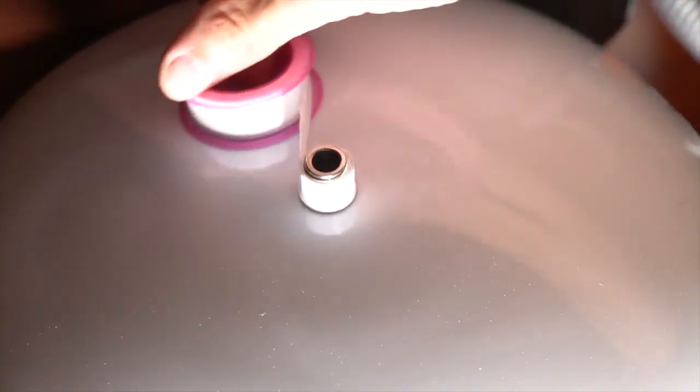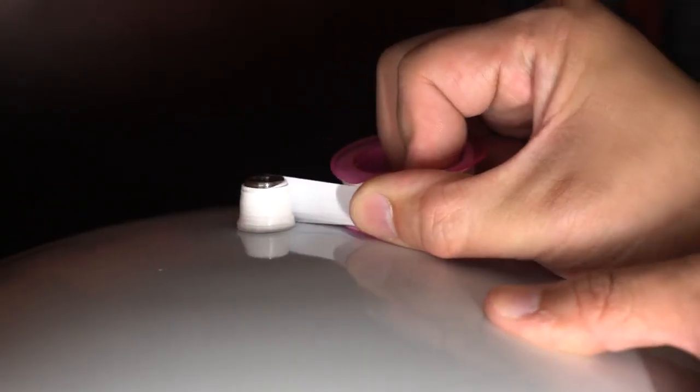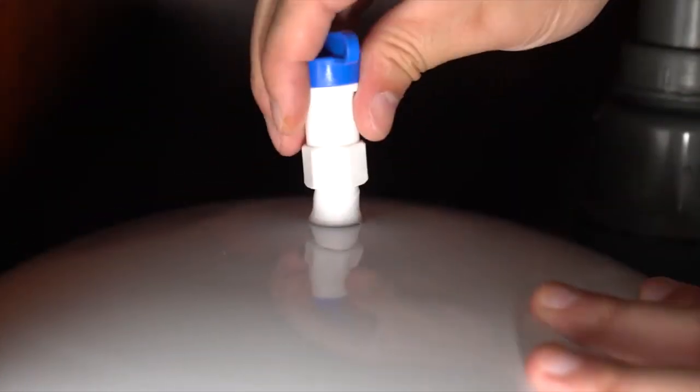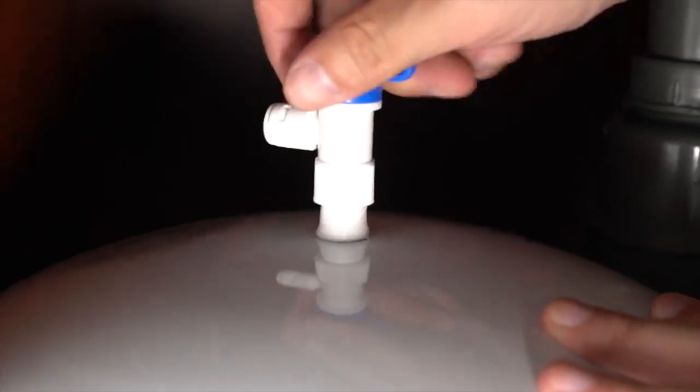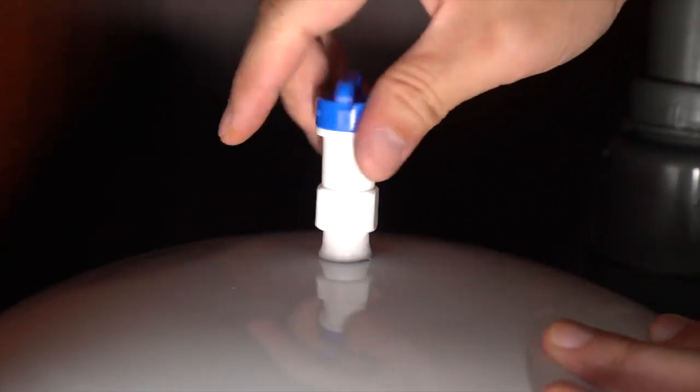Water Pressure Tank: Locate the pressure storage tank and apply Teflon tape in a clockwise direction to the thread for 10 turns. Hand tighten the tank ball valve onto the thread. Do not over tighten. It does not need to be very tight to obtain a watertight seal.